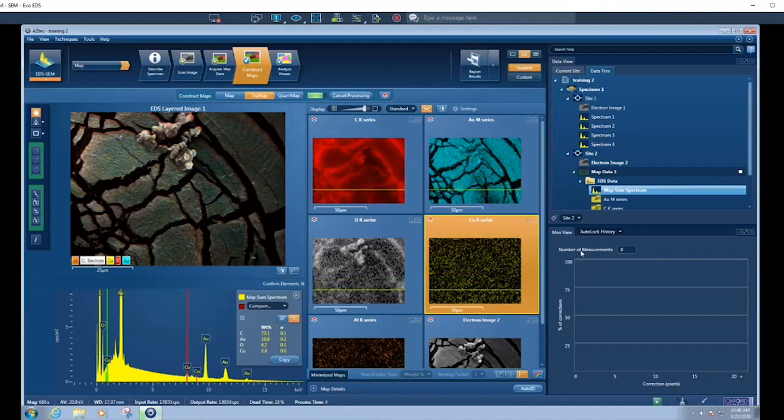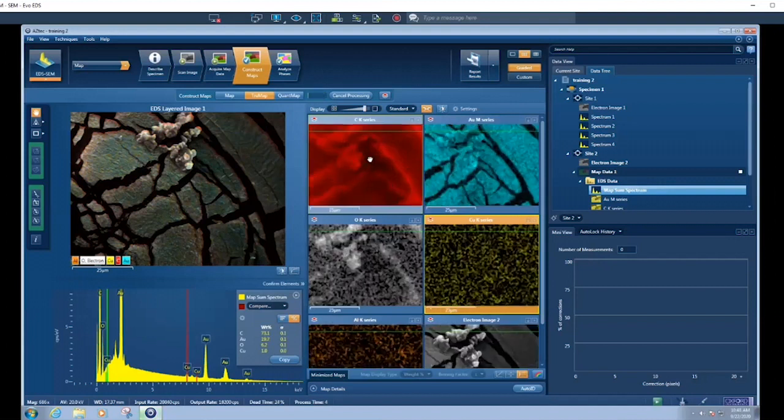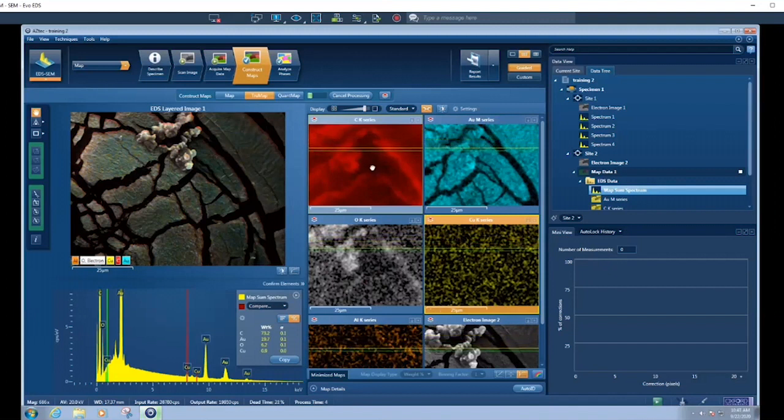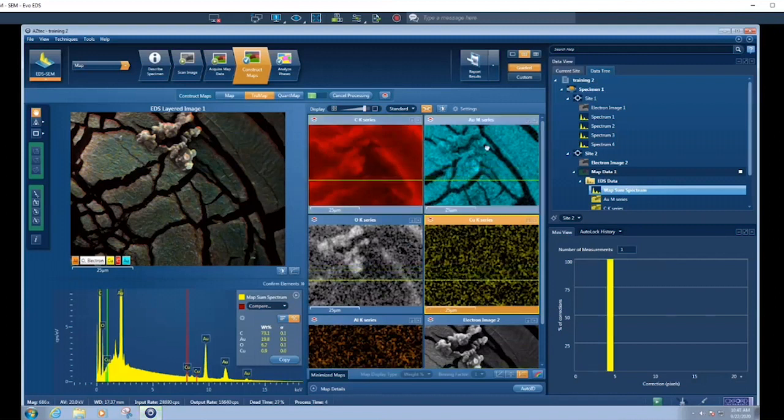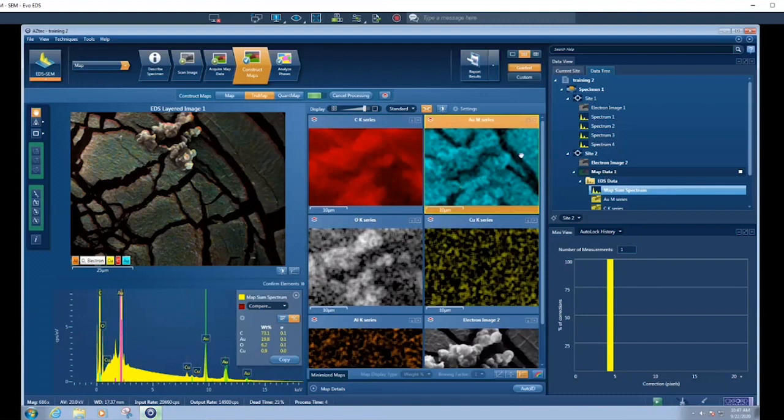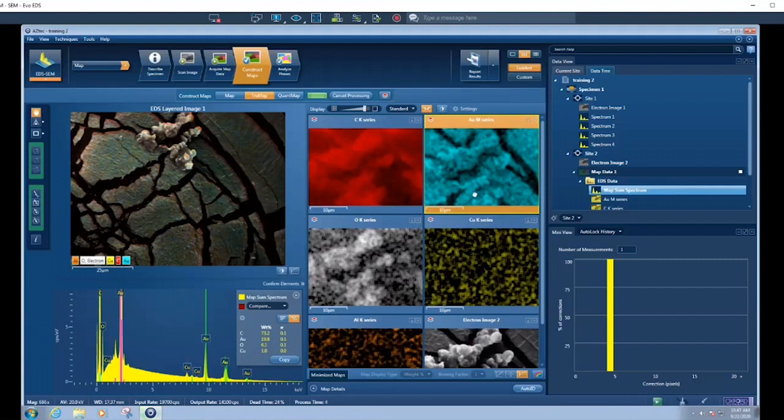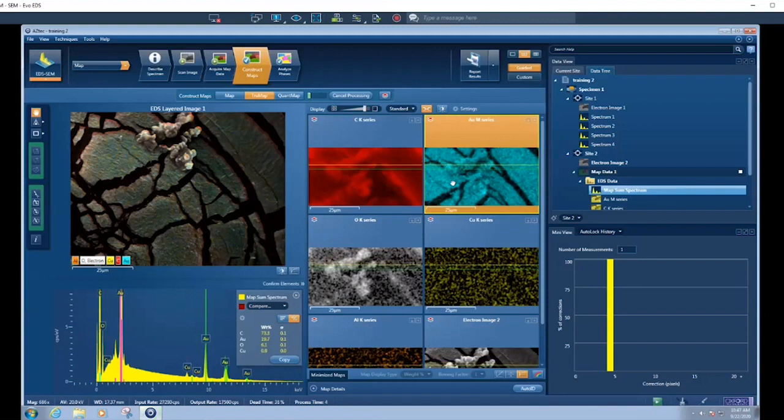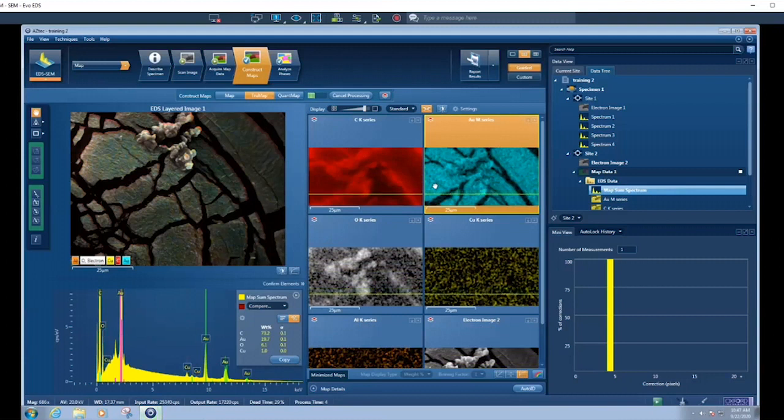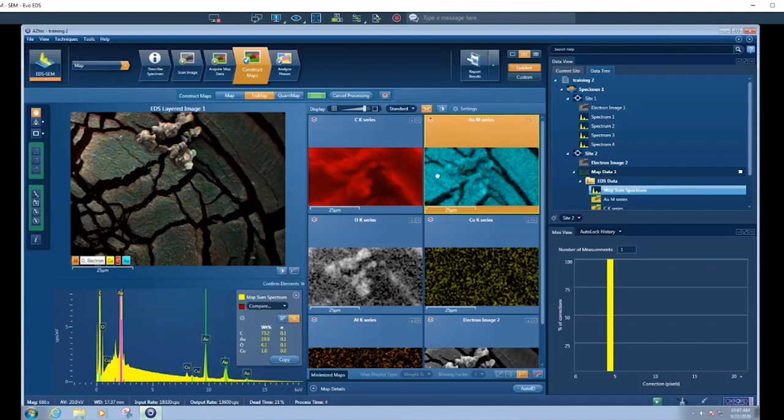As you said, this is the area that is the uneven one. So where's an example that you can see? Take the carbon for example, underneath this particle. See how it's not giving out as much signal? In here it's hard to tell a little bit, but you can see that this should theoretically have all the same amount of gold. But around here it looks a little bit less bright in gold because there's less signal coming through. If we let it count a little bit longer, it'll become more obvious. Also, these particles aren't massive, they're not huge, so it's not shadowing as much. But the larger the surface topography, the more the shadow. You can see here a little bit it's coming through, but on this side it's a little bit dimmer because there's less signal coming through.